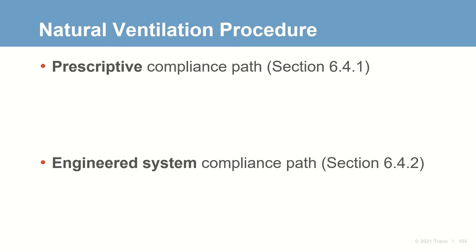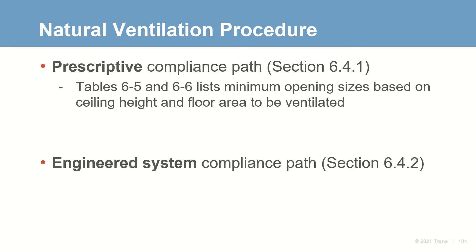This procedure includes two compliance paths: a prescriptive path and an engineered system path. When using the prescriptive path, you look up the minimum required sizes of natural ventilation openings in a table, based on ceiling height and the floor area to be ventilated.